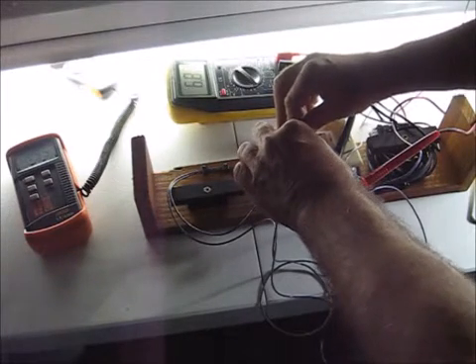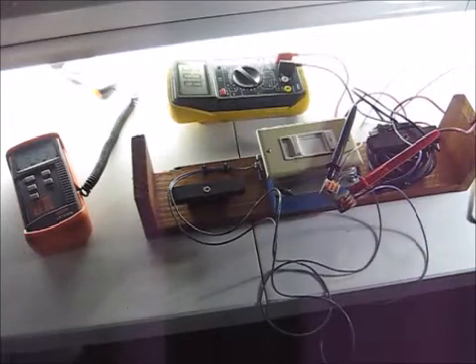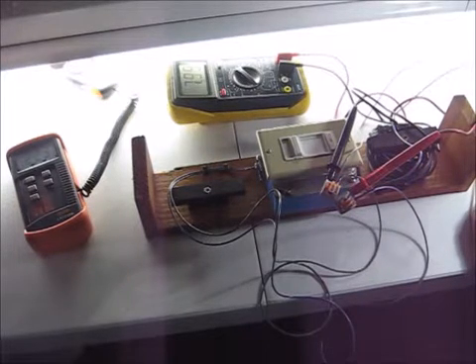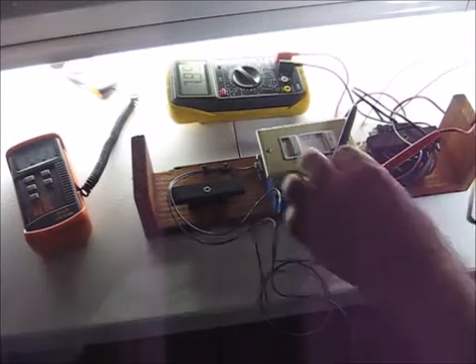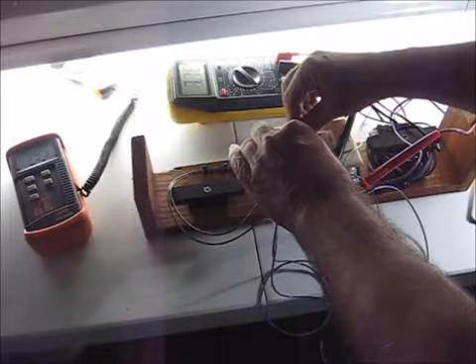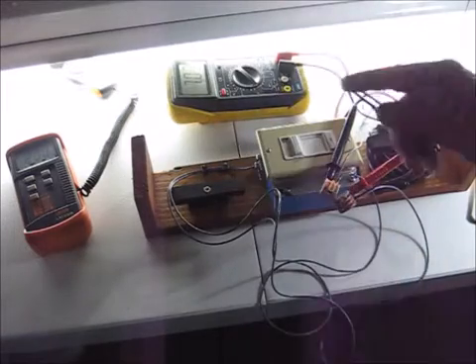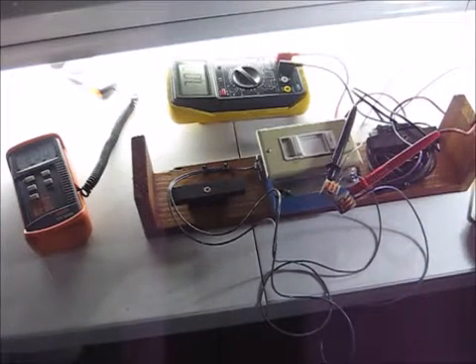So let's bring it down to 8 volts of control voltage. That's 8 volts right there. I've got 223 reading on my foot candle meter. I'm going to take it down to 7 volts. There we go. I've got about 200 foot candles even.